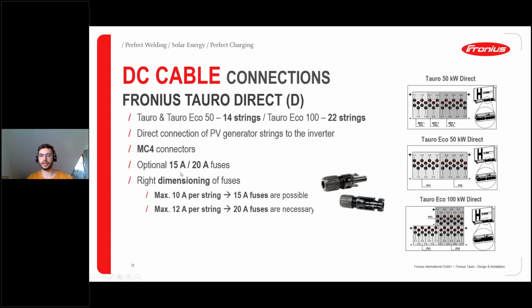There is the option to integrate fuses again. So you can choose between 15 amp or 20 amp fuses. That's of course depending on the right dimensioning. So on the module you're using, for example, on a 10 amp string, on a maximum of 10 amp per string, you would use the 15 amp fuses. If you have 12 amp per string, you would go for the 20 amp fuses.